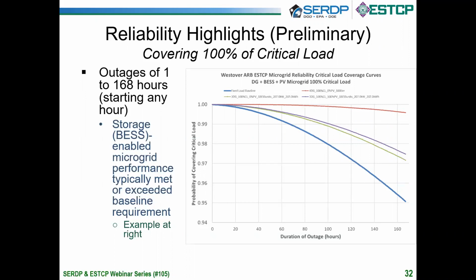The baseline requirement is the blue line here, and if no diesel generators are removed, the battery-enabled microgrid performs at the red line. So that's the result when the investigator added the battery and did not deduct diesel generators. And you can see it's almost perfect for the entire duration, and well above the baseline and even farther above the likely performance of standalone backup generators.